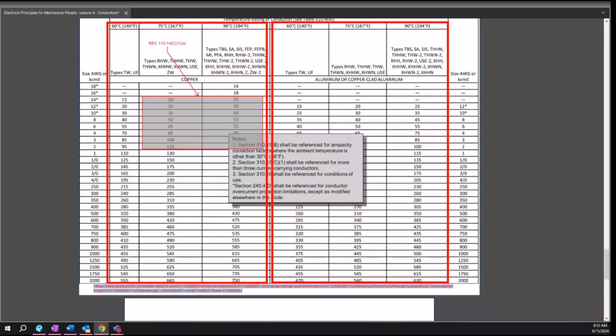Yes. Why do they give it if you cannot use it? Because there are still instances where, if you know for sure that the terminals you're landing on are rated for 75C, great, you can totally use it. And that's why I said, I recommend putting it in pencil so that you can still read it. Gotcha. But if you do not know, you should assume that they are not rated for that and they're rated for 60C. Yes, because there's exceptions in there saying, if this, then 75C is fine. But unless you can verify this, or this, you have to use 60C.